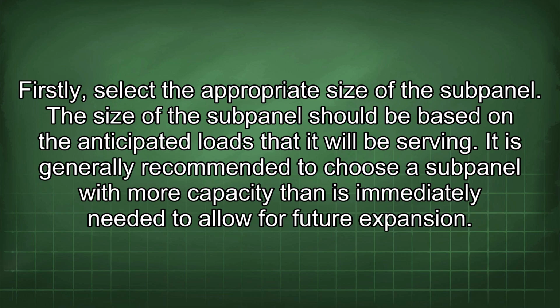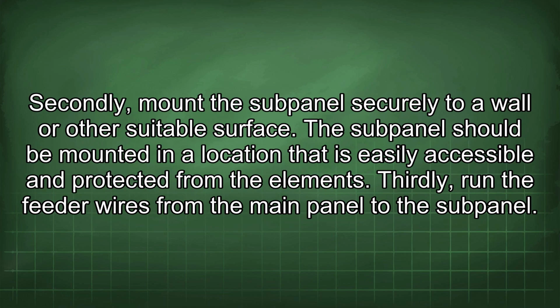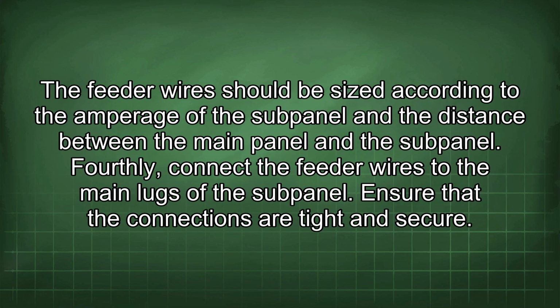It is generally recommended to choose a subpanel with more capacity than is immediately needed to allow for future expansion. Secondly, mount the subpanel securely to a wall or other suitable surface. The subpanel should be mounted in a location that is easily accessible and protected from the elements. Thirdly, run the feeder wires from the main panel to the subpanel. The feeder wires should be sized according to the amperage of the subpanel and the distance between the main panel and the subpanel. Fourthly, connect the feeder wires to the main lugs of the subpanel. Ensure that the connections are tight and secure.